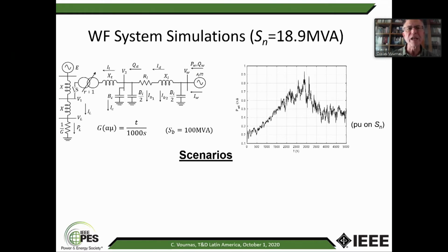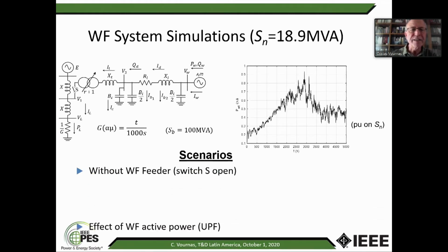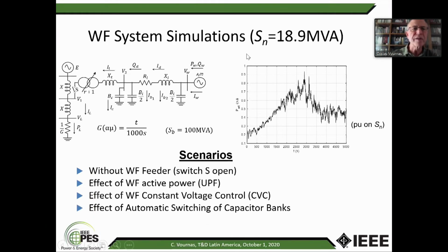So here is one simulation for this simple radial system we were discussing before. I'm giving you the nominal of the wind farm, which is close to 19 MVA, just to show you the effect on the maximum power compared to the capacity of the wind farm. Because if you have a large wind farm, you can have a larger effect and vice versa. So we'll take several scenarios: without the feeder, just a reference scenario, with the switch closed and the variable wind power and unity power factor, just to show the effect of the wind active power on the maximum power transfer.